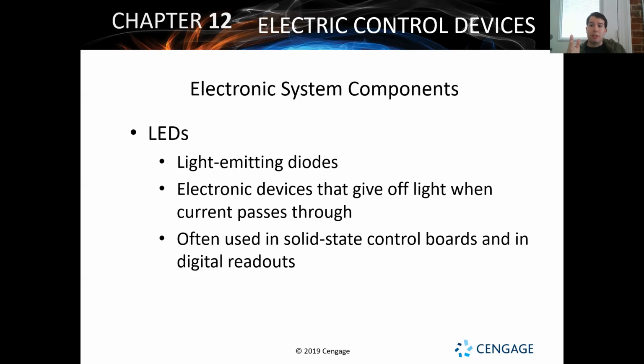Now, if you go to a system and it's failed, you want to look at that LED and count the number of flashes. Typically it's two sets of flash numbers - one set of slow blinks, so it'll be like 1, 2, and then fast blinks. So you'd count, okay, I had 4 slow blinks, I had 6 fast blinks, so 46 would be my error code. Again, some of them are backwards - fast blinks might be the first number and slow blinks the second. It just depends on the manufacturer.